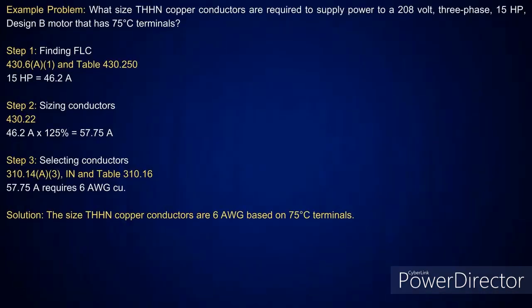This one here is a 3-phase, the exact same thing. I've got a 208 volt 3-phase 15 horsepower design B motor. Go over to table 430.250. 15 horsepower is going to require 46.2 amps. And step 2, we take it at what? 125%. That'll give me 57.75 amps. Go to table 310.16, 75-degree C column. The next size above that is 65 amps, which requires a number 6 conductor.